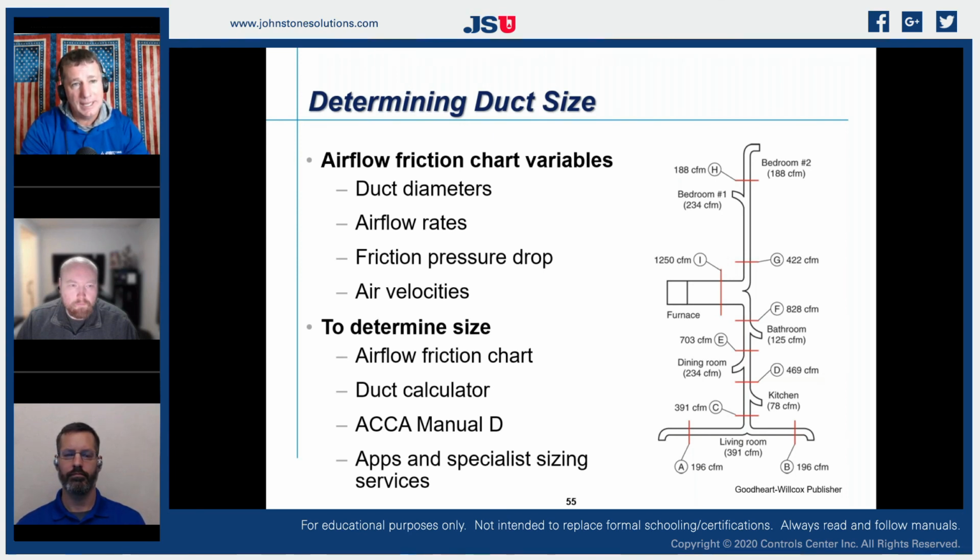But as we talk next week, we're going to look at how if we want to keep that exactly 0.5, we have to know other factors. We have to know how much drop we have on our coil, how much drop we have on our filter, how much drop we have on a secondary heat exchanger, any of our IAQ products, all of our elbows. And that's when we factor in the total effective length. And then we can get a new friction rate based on that. But for most of my design, I use 0.1 on supply and 0.08 on return, and that gets my average sizing.